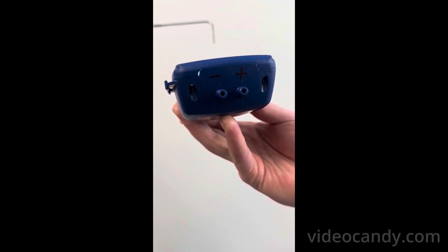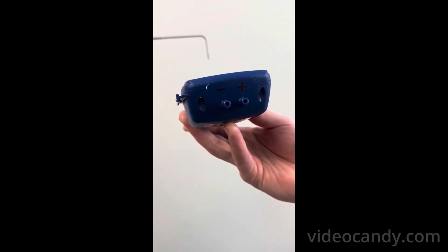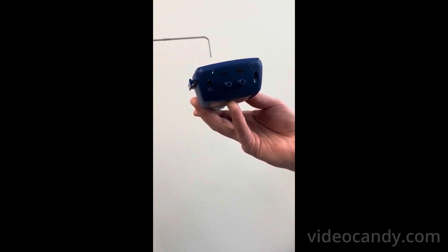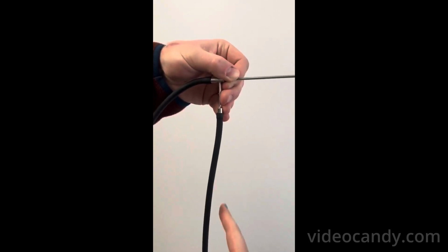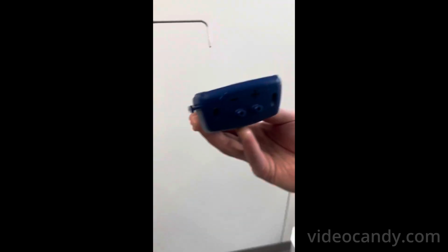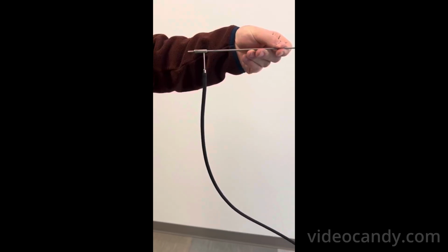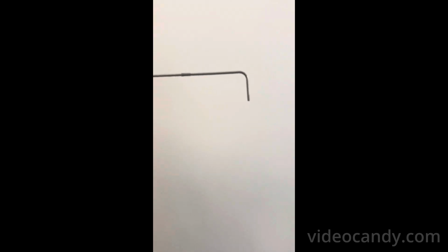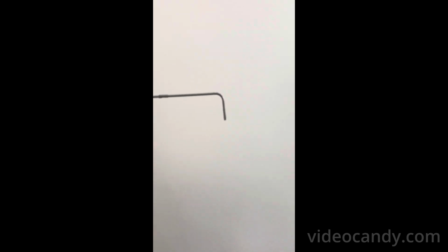Also, on your device, you have a positive and a negative terminal. These are marked really small in plastic on the device, but we penciled them in with a Sharpie to make them easier to see. In order to measure static pressure, you're going to take only one tube on the wall side of the pitot tube and plug it into your negative terminal. Once you have your pitot tube set up like this, with the one tube connected to the wall pressure measurement and into your device, you can then stick this end of the pitot tube into your duct and take a centerline measurement. The value read on the screen will be that of your static pressure.